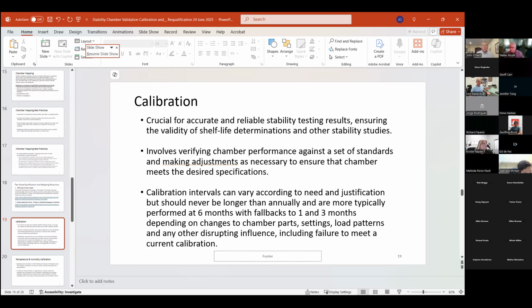And the intervals can vary according to need and justification, but should never be longer than annually, and are much more typically performed at 6 months with fallbacks to 1 and 3, depending on changes to chamber parts, settings, load patterns, and any other disrupting influences, including failure to meet a current calibration. So a lot of companies will rely on the longer range things, and if they're lucky, then not much changes. But if you experience a failure in calibration at a shorter interval, you're kind of out there in the wind, trying to prove that your product is still good. It was exposed to the things it was supposed to be exposed to in temperature and humidity.